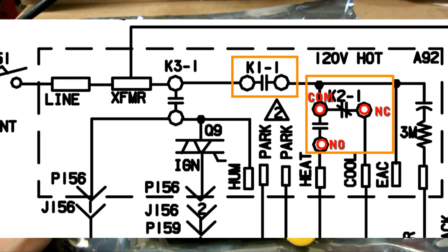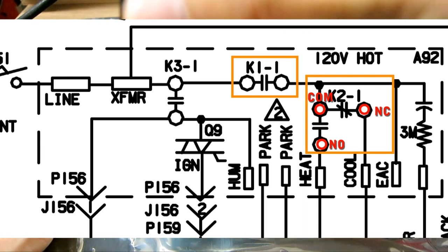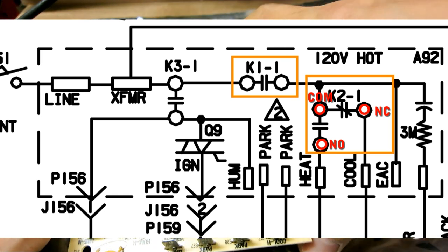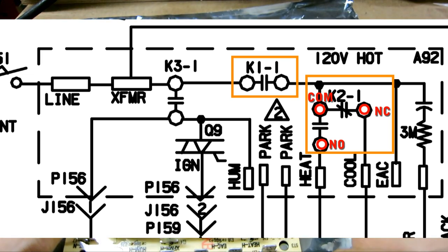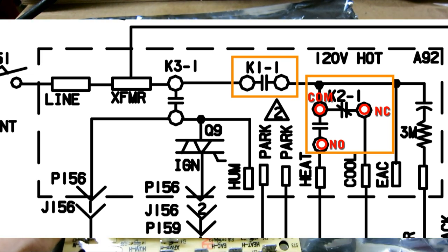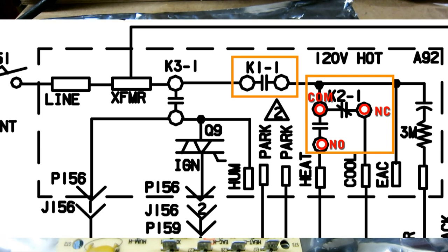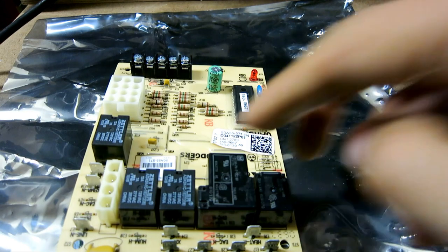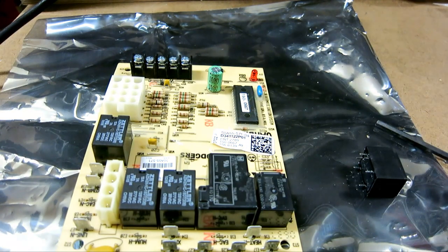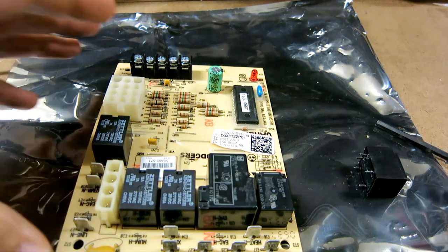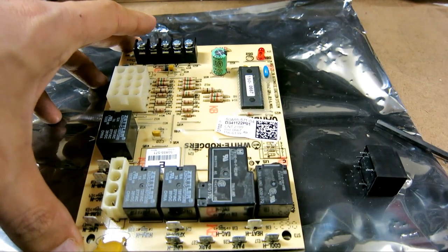by probing around, I realized that there's only two relays that controls the Cool H and Heat H line. So it's either these two relays, or the board itself is bad. So I'm just going to go ahead and try to replace these two relays.